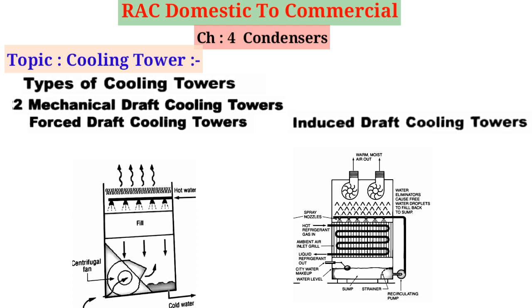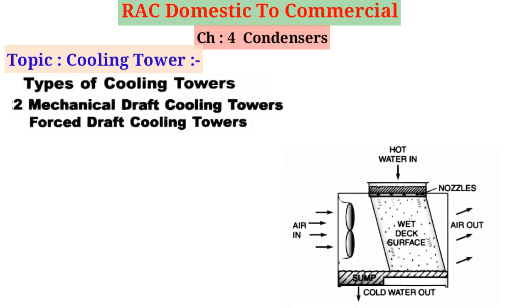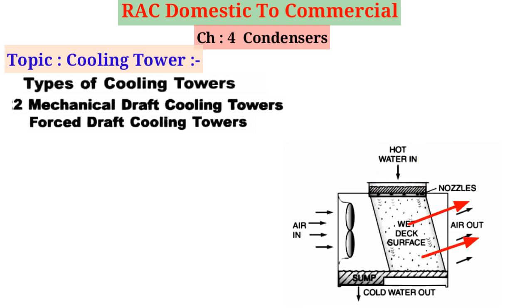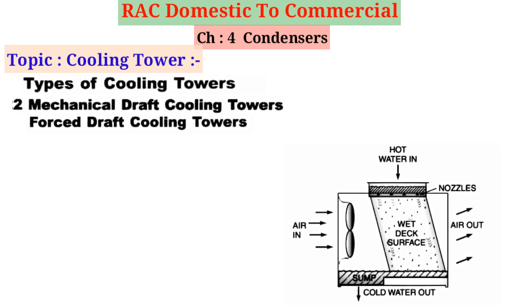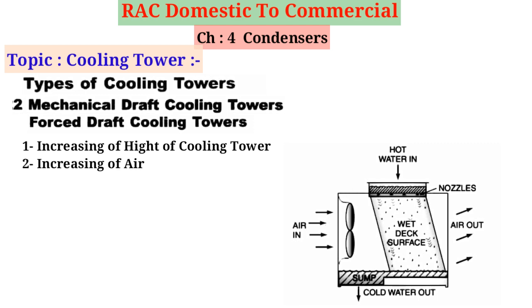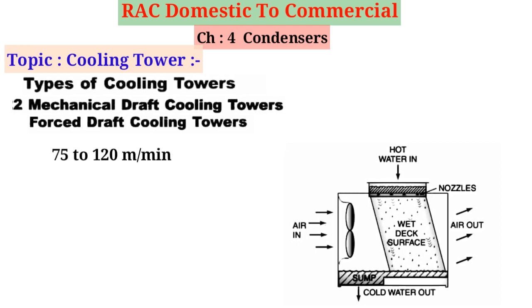In forced draft cooling towers, a fan forces the air through the tower. The warm water from the condenser is sprayed at the top of the tower through spray nozzles. Air is forced upward through the side near the bottom of the tower. The condenser warm water is cooled by evaporation as discussed earlier. The effectiveness may be improved by increasing the height of the tower, the area of water surface exposed to air, or the velocity of air. An air velocity of 75 to 120 m per minute is recommended, with a flow of 90 to 120 cubic meters per minute per ton of refrigeration capacity.